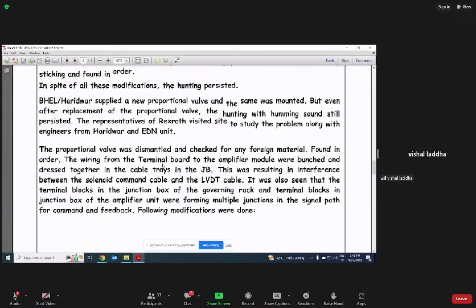The wiring from the terminal board to the amplifier module was bunched and dressed together in cable trays in the JB. This is the modification after they came to the site. And this was resulting in interference between the solenoid command cable and the LVDT cable. Yes, this is the reason. This is from the JB to the proportional valve.